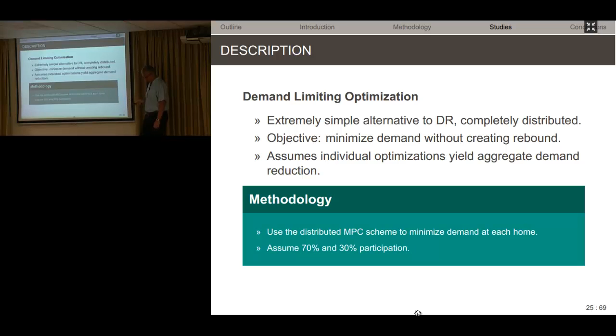One of the things I want to point out is that for this analysis, during occupied times, we're allowing the occupied lower bound to be 2 Kelvin below the set point, but not above the normal set point. So during occupied times, we're allowing to pre-cool a little bit, and during unoccupied times, we're allowing the temperature set point to be raised by 3 and lowered by 5.